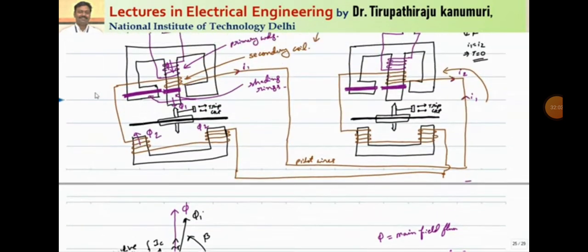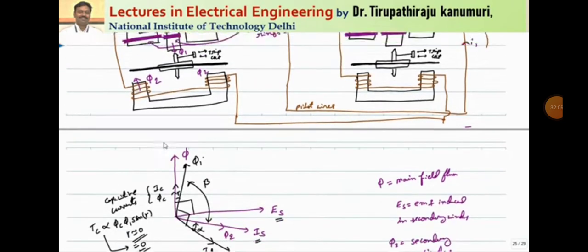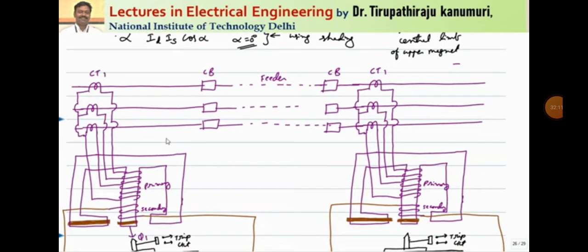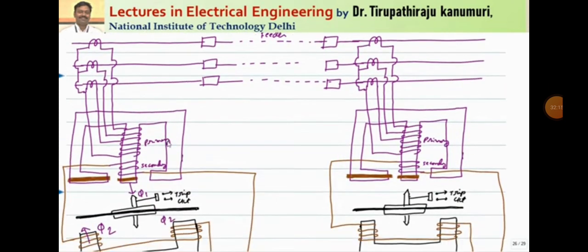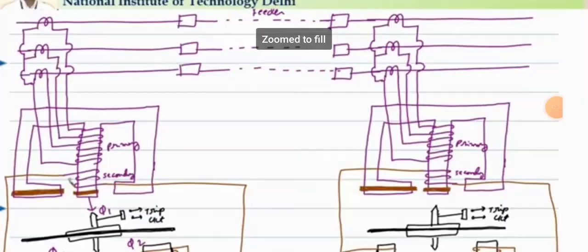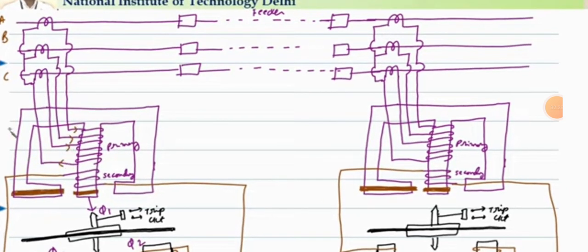The shading provided on the left-hand side provides the restraining or biasing torque. For the three-phase circuit, we go for the summing transformer. The primary is connected to the three phases, and the respective currents Ia, Ib, and Ic pass and return back. Under external fault conditions or normal conditions, the same currents are induced in both circuits, so the effect is the same on both sides and no circulating currents pass. The effect of capacitance is nullified by the shading ring in the central limb.